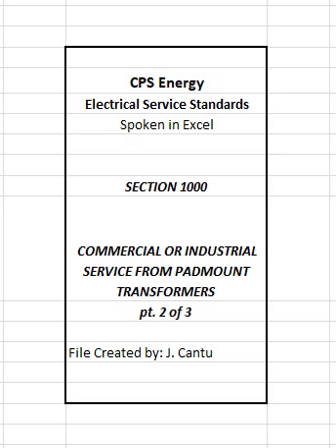Where customer elects to install cables in excess of that allowed by CPS Energy, the cables shall terminate in a customer-furnished and installed tap box pre-approved by CPS Energy, refer to D below. 1. Customer shall furnish single barrel, 2-hole tongue lugs. Mounting holes in tongue to be 9/16 inches and spaced vertically and horizontally 1 3/4 inches center to center. Cable lug width shall not exceed 1 3/4 inches and height shall not exceed 2 1/4 inches.